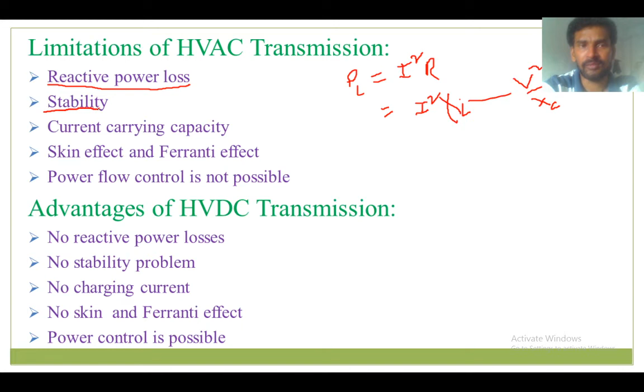Second criteria is stability. Stability is one of the main concerns in case of HVAC transmission system. As we all know, if we draw the P-delta curve, this is delta load angle and this is real power. Actually, the real power formula for a synchronous machine is E into V by XS sin delta. So once the line is designed, this XS will not change. But this E, V and delta, this real power depends on this sin delta. So if I draw the curve between P and delta, it will be like this. The real power will be maximum at this delta, this is delta max. At this delta max, we will get maximum real power. This is P max.